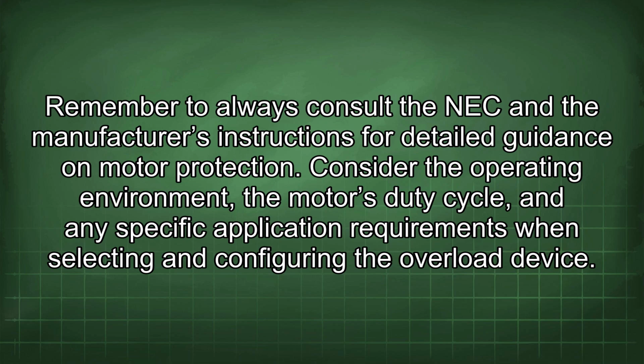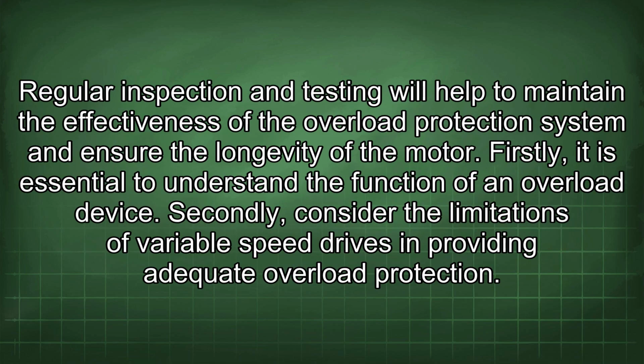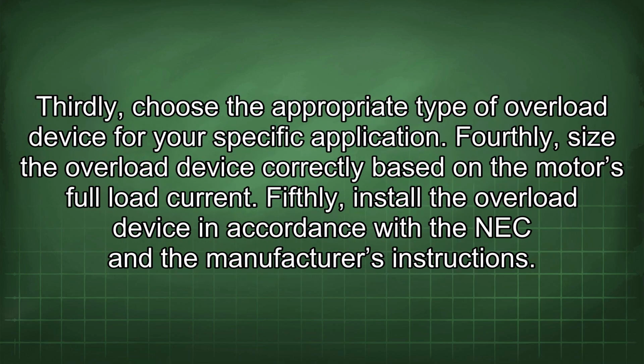Consider the operating environment, the motor's duty cycle, and any specific application requirements when selecting and configuring the overload device. Regular inspection and testing will help to maintain the effectiveness of the overload protection system and ensure the longevity of the motor. Firstly, it is essential to understand the function of an overload device. Secondly, consider the limitations of variable speed drives in providing adequate overload protection. Thirdly, choose the appropriate type of overload device for your specific application. Fourthly, size the overload device correctly based on the motor's full load current.